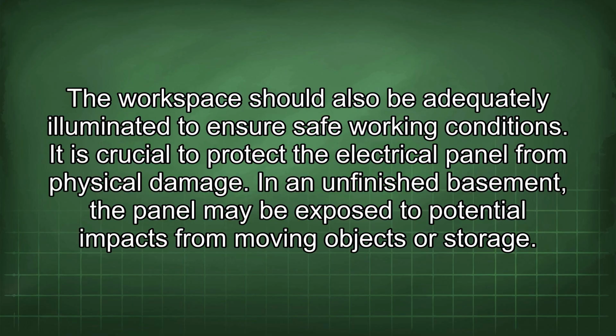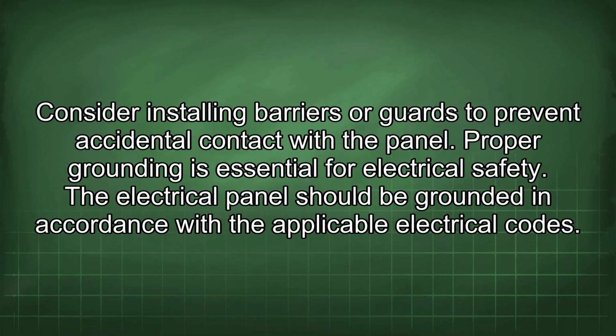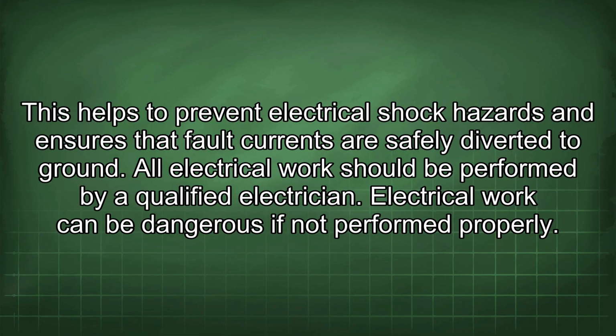It is crucial to protect the electrical panel from physical damage. In an unfinished basement, the panel may be exposed to potential impacts from moving objects or storage. Consider installing barriers or guards to prevent accidental contact with the panel. Proper grounding is essential for electrical safety. The electrical panel should be grounded in accordance with the applicable electrical codes. This helps to prevent electrical shock hazards and ensures that fault currents are safely diverted to ground.